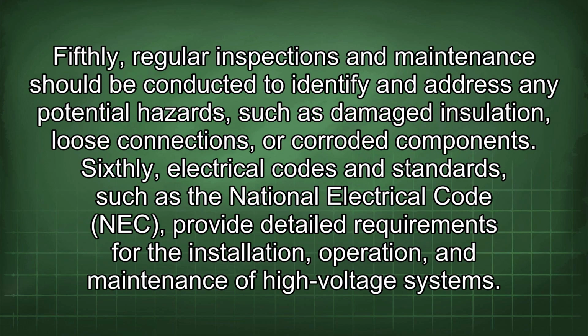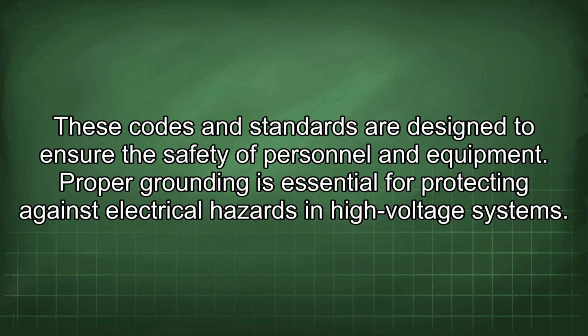Fifthly, regular inspections and maintenance should be conducted to identify and address any potential hazards such as damaged insulation, loose connections, or corroded components. Sixthly, electrical codes and standards such as the National Electrical Code (NEC) provide detailed requirements for the installation, operation, and maintenance of high-voltage systems. These codes and standards are designed to ensure the safety of personnel and equipment. Proper grounding is essential for protecting against electrical hazards in high-voltage systems.